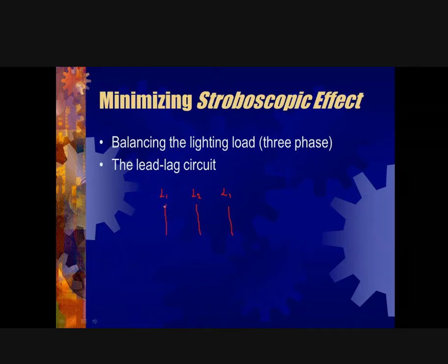Because remember, if it's a three-phase facility, most likely one of the legs is going to be 190. We do not utilize that 190 with neutral. If we're talking about 110 lights, we're going to use the legs that are not 190, along with our neutral.